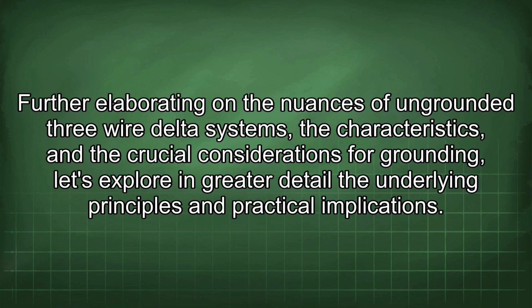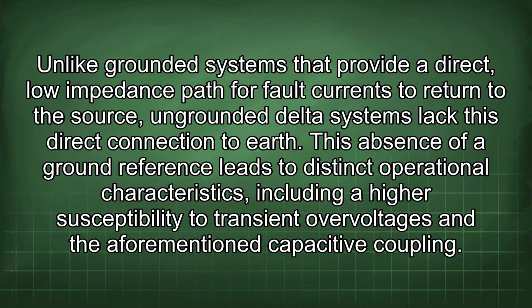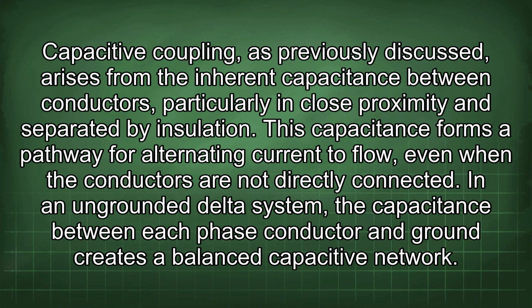Further elaborating on the nuances of ungrounded three-wire delta systems, the characteristics, and the crucial considerations for grounding, let's explore in greater detail the underlying principles and practical implications. Unlike grounded systems that provide a direct, low-impedance path for fault currents to return to the source, ungrounded delta systems lack this direct connection to Earth. This absence of a ground reference leads to distinct operational characteristics, including a higher susceptibility to transient overvoltages and the aforementioned capacitive coupling. Capacitive coupling, as previously discussed, arises from the inherent capacitance between conductors, particularly in close proximity and separated by insulation. This capacitance forms a pathway for alternating current to flow, even when the conductors are not directly connected.